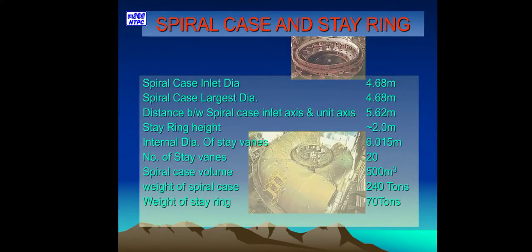Spiral case and stay ring specifications: Spiral case inlet diameter 4.68 m; largest diameter 4.68 m; distance between spiral case inlet axis and unit axis 5.62 m. Stay ring height 2.0 m; internal diameter of stay vanes 6.015 m; number of stay vanes 20. Spiral case volume 500 m³; weight of spiral case 240 t; weight of stay ring 70 t.